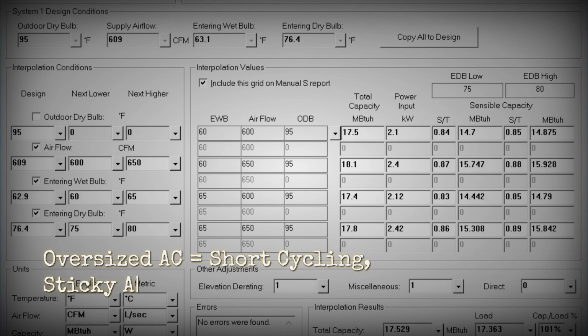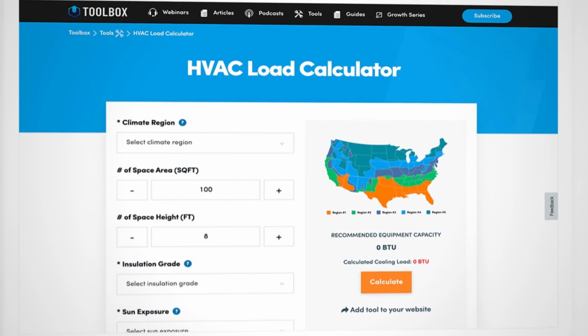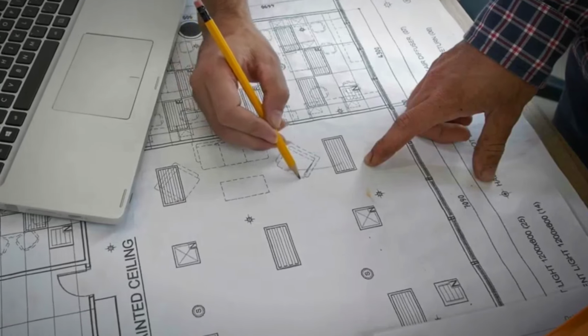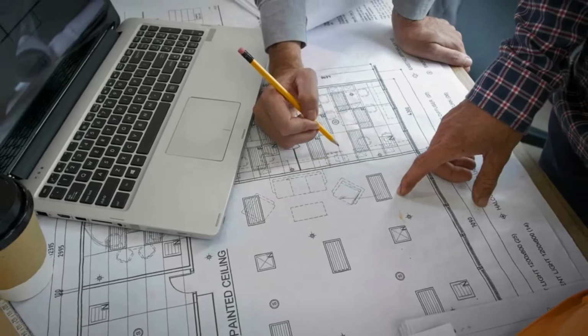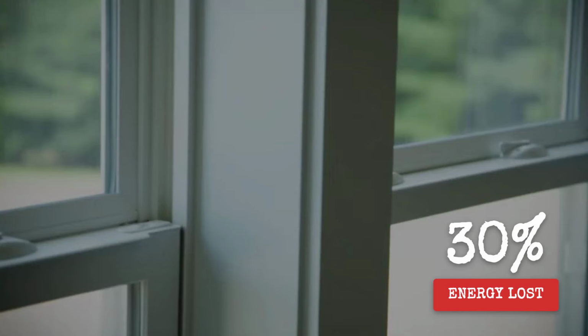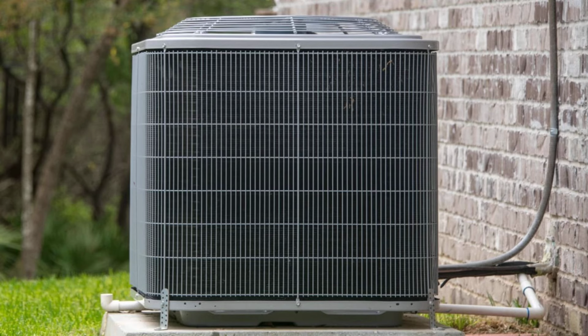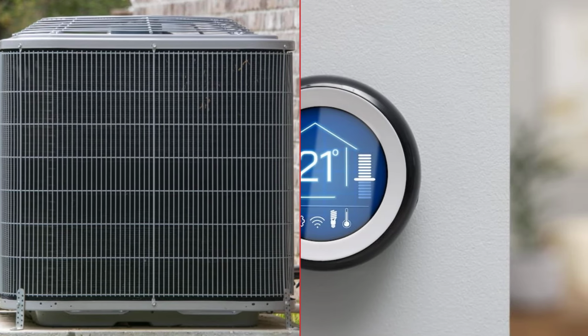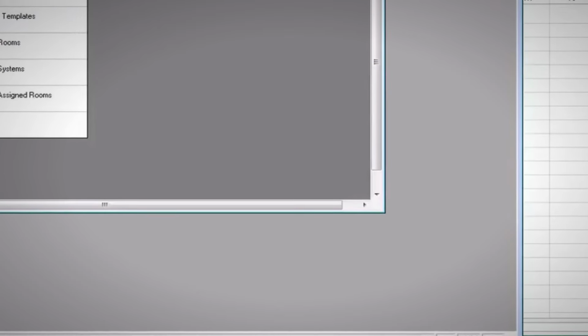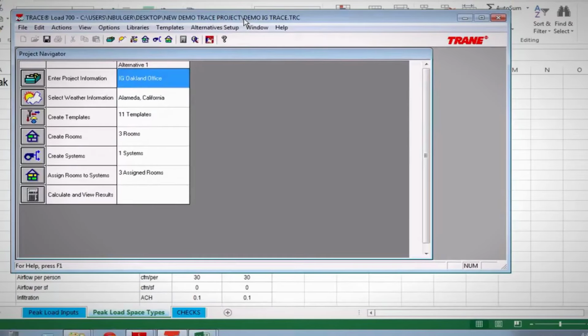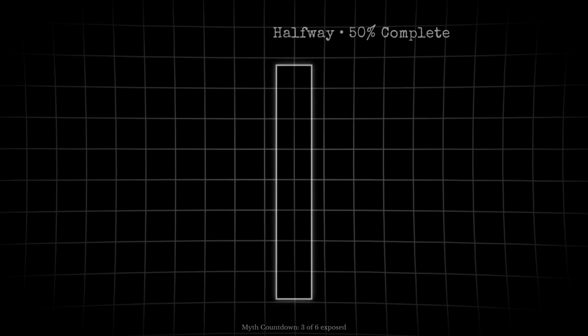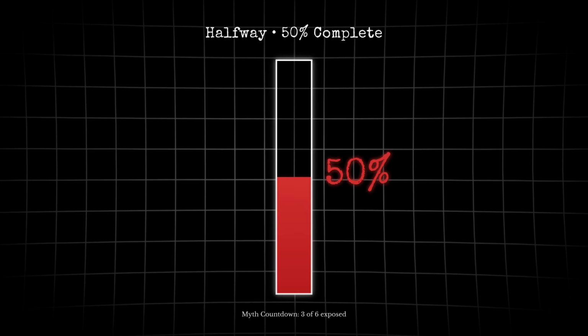Because most builders skip the manual J load calculation, the formula that determines exactly how much heating and cooling your house needs. Instead, they use a rule of thumb, 1 ton per 500 square feet, and often round up. That safe guess is often a full ton too large. Technicians size their own systems to the calculation, not to a rule of thumb. That was number 3, and we are halfway through.